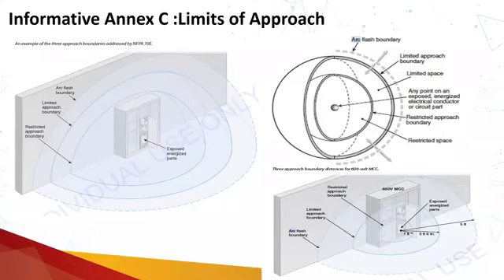So putting it simply, if the doors are closed and secure, there is no exposed bus bar or conductors, and no one is interacting with the electrical installation, these boundaries do not exist. You can have a limit of approach related to your own guidelines and safety, but you cannot say that this is an arc flash boundary, a limited approach boundary, or a restricted approach boundary. Okay, if it is closed, but someone is performing switching operations remotely using a SCADA or RTU, the boundaries will be in place. That is, no person should be within the arc flash boundary.